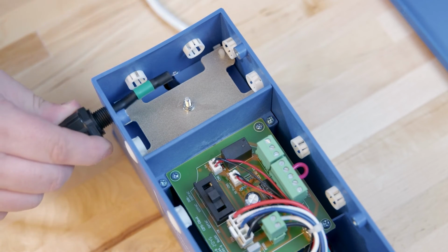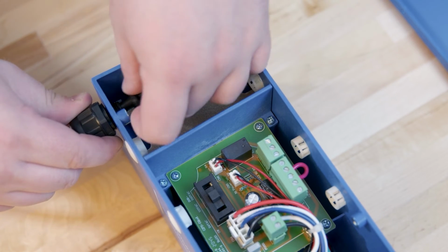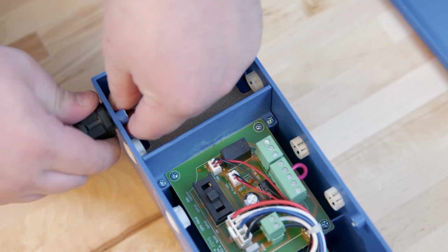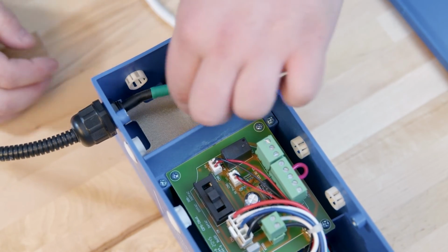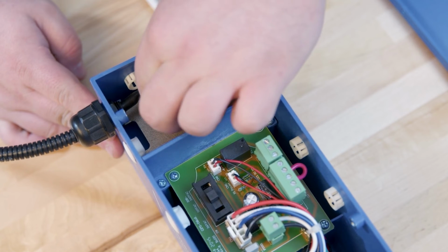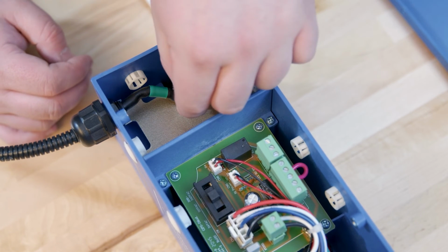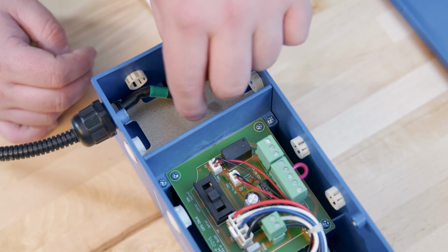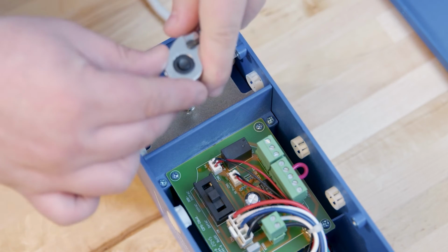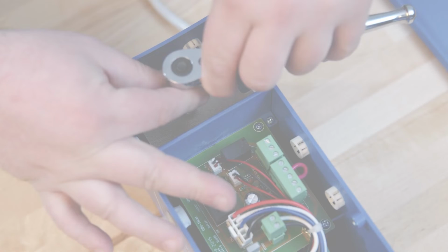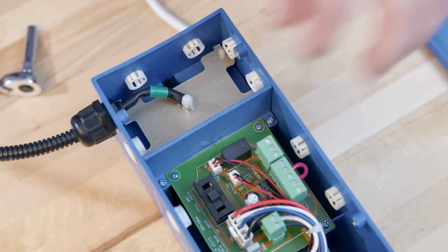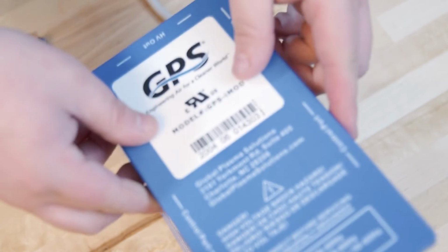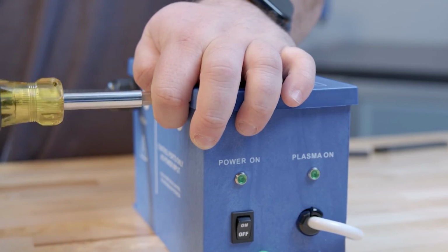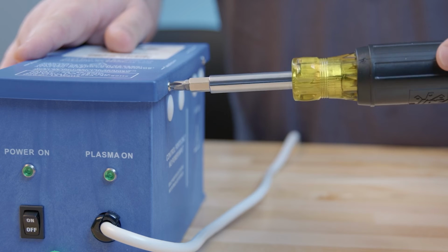Thread the high voltage cable through the port of the power supply and secure the retaining nut of the cable gland. Place the ring terminal connector onto the high voltage post. Reinstall the top nut and secure it using the deep 7mm socket. Ensure you do not over-torque the top nut, as this can damage the product. Reinstall the acorn nut. Place the lid back onto the power supply and secure with 4 machine screws.